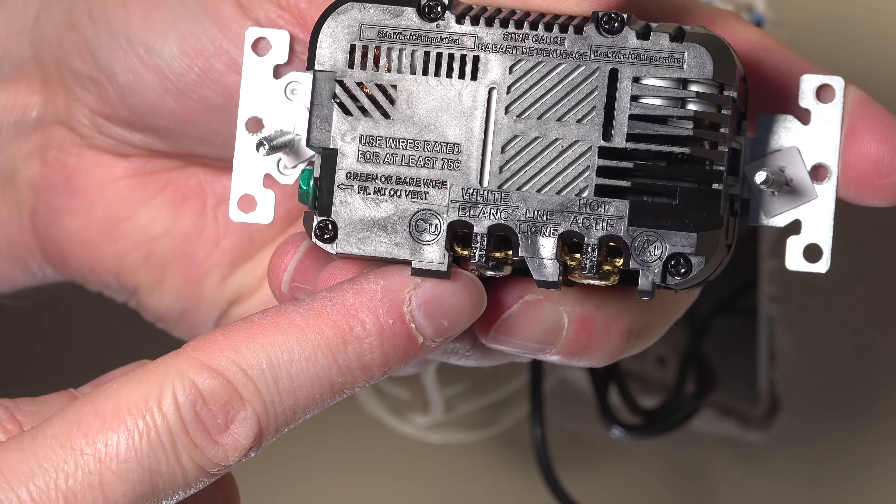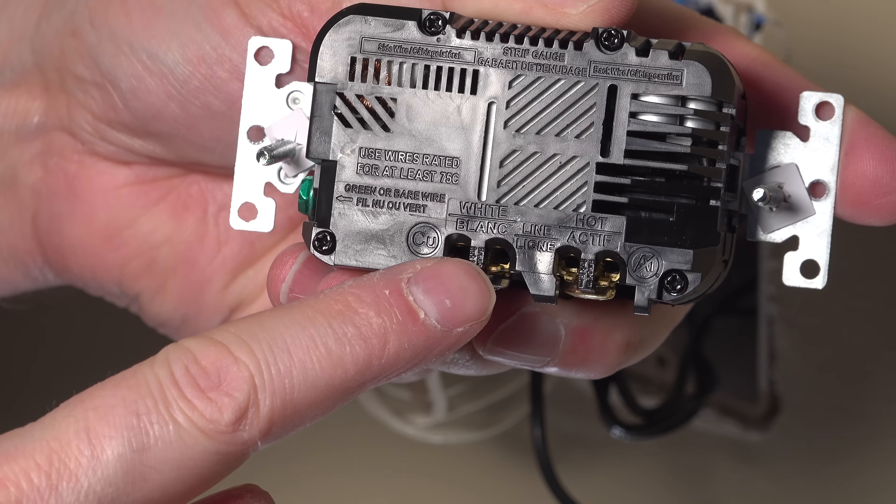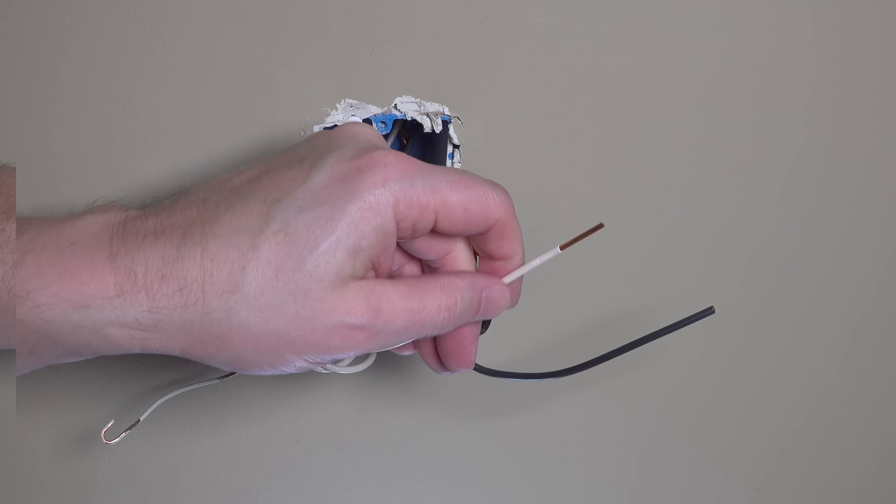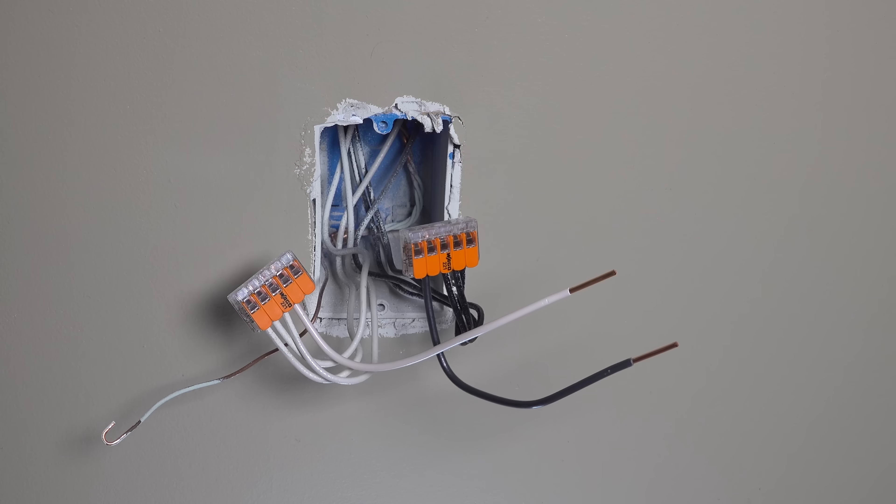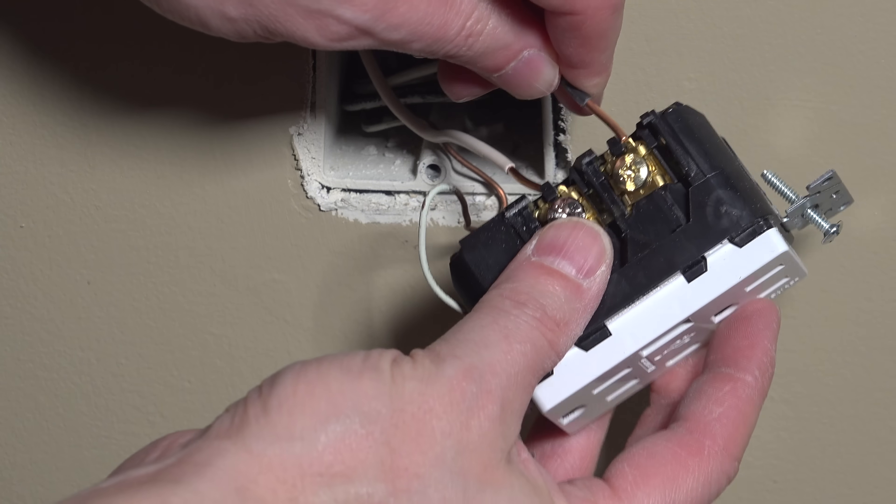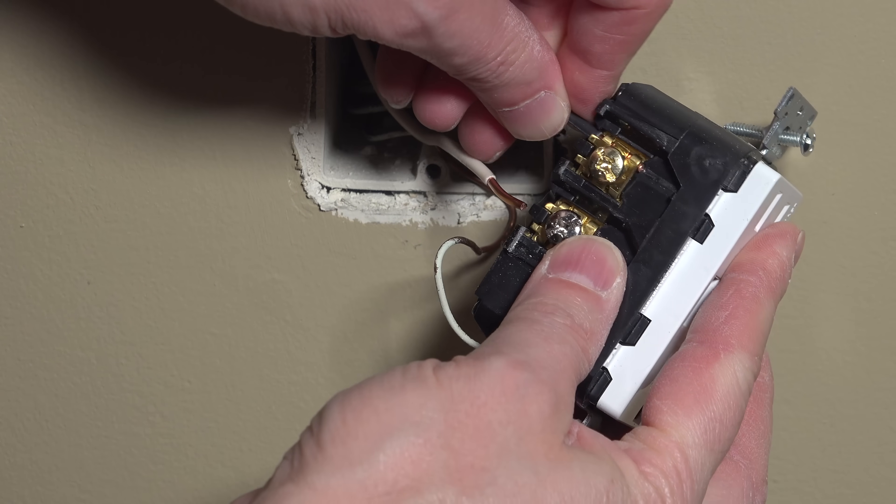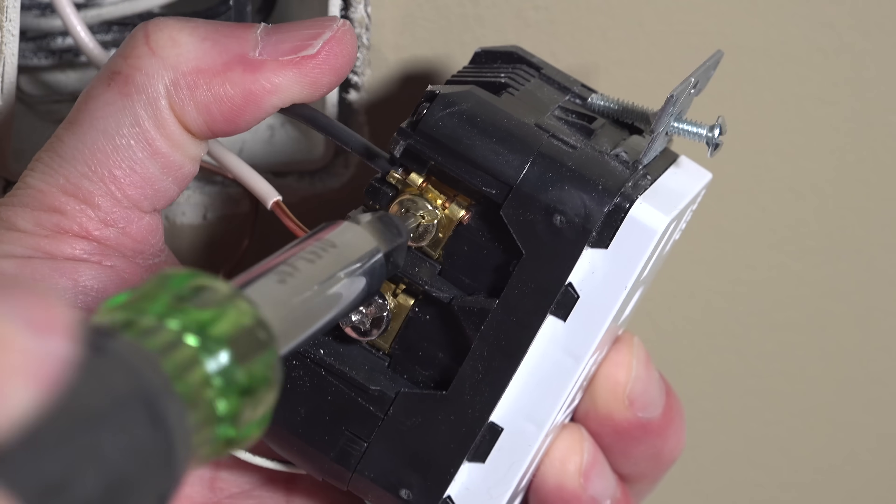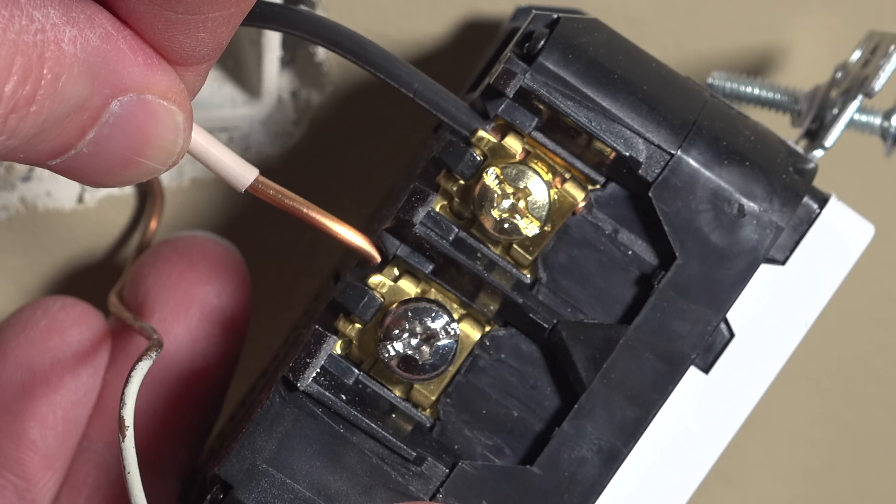You want to make sure that you go to the right screw. There's going to be a silver one and a gold one. The gold is going to go to the hot or the black wire, and the silver is going to go to your white or neutral wire. And connecting it to this model is really easy. You just insert the wire into the side clamp and screw it down tight. This eliminates the need to loop your wires, but if you want to do that method, you can also choose that as well.